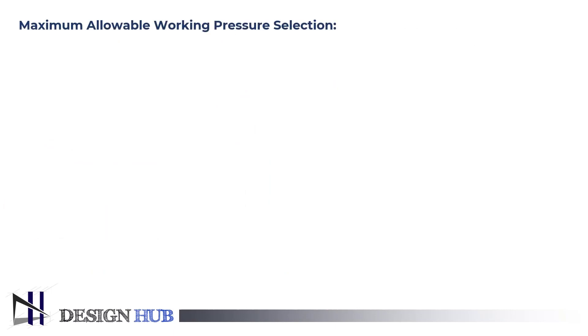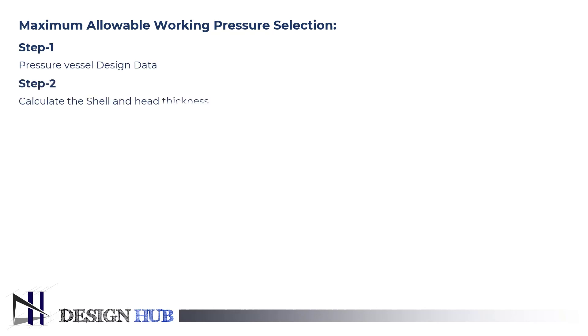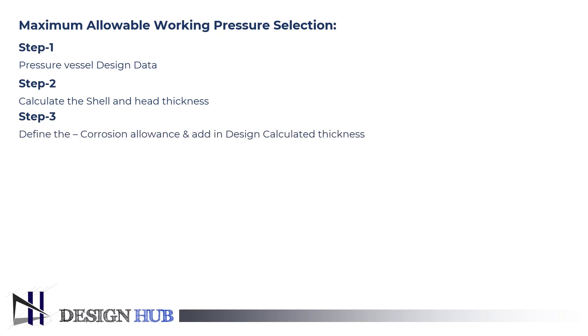Let us see how the selection of maximum allowable working pressure is done. The first step is to have pressure vessel design data, so as to be able to calculate the shell and head thickness. Then one should define corrosion allowance and add the calculated design thickness. Then add corrosion allowance and design thickness to get the total thickness.